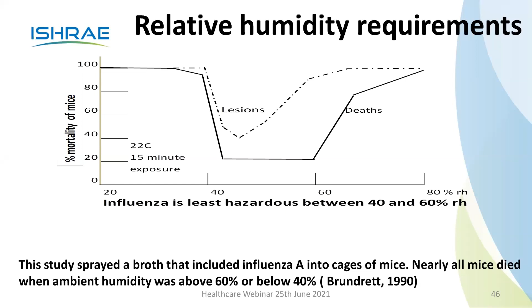Then at 40 to 60%, the fatality rate is much, much lower. You can see that the mortality rate has dropped to 20%. Then from 60 to 80%, again, the mortality rate is going up. So what this chart shows, and it is not just this chart, so many studies are there, is that the 40 to 60% range is ideal for the well-being of people. So that is why it is recommended that you should have 40 to 60% in hospitals.